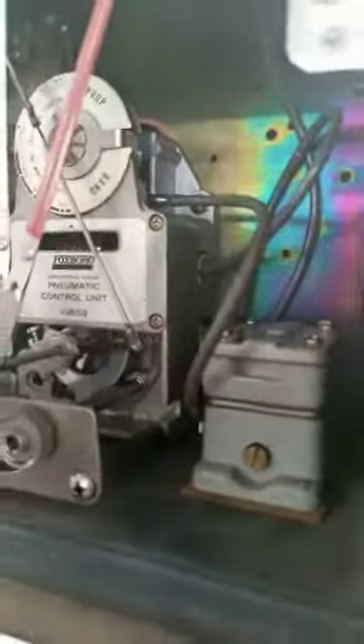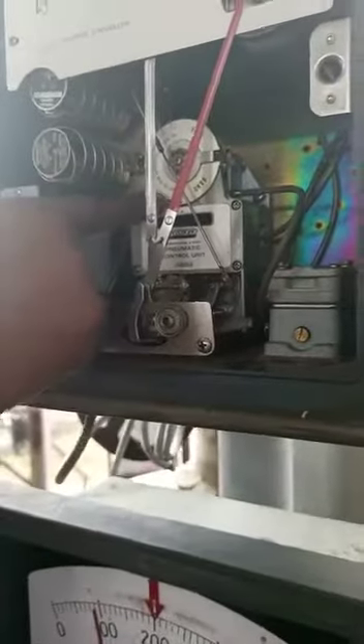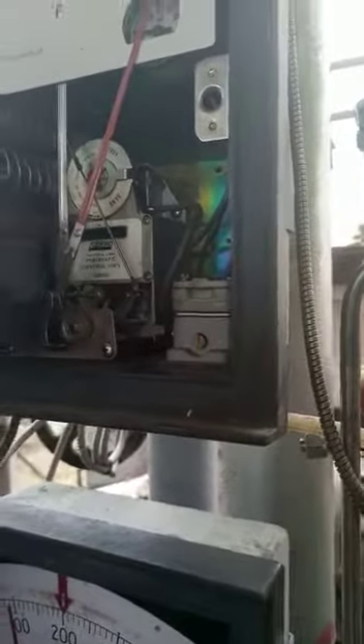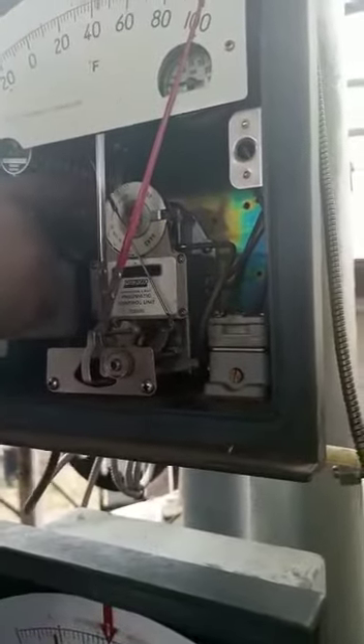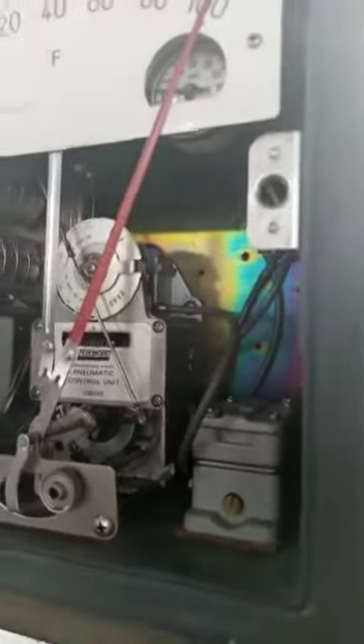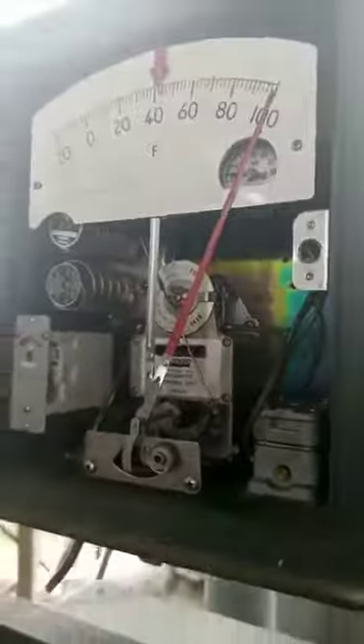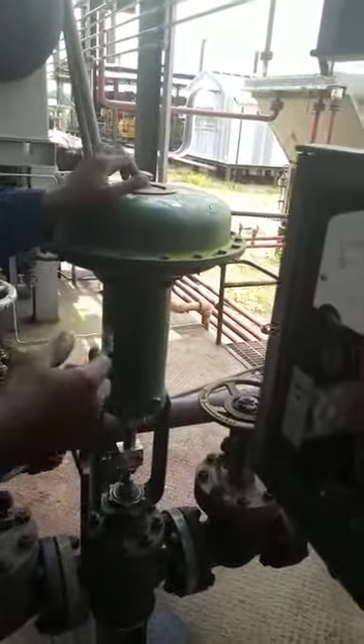If you want the temperature controller to sense the heat at which it will open the valve or close the valve, this is the place we touch. If you want higher sensitivity, you take it to this angle. If you want lower, you come back to this point. For higher sensitivity, immediately the temperature controller senses the heat, it will authorize the pneumatic valve to shut down or open up, depending on the situation and the process that you want. So we are going back to 100. Going to 100 now.